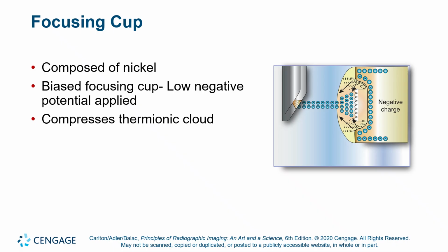Okay. Keeping the thermionic cloud, or the space charge as it's called, small allows us to keep the focal spot small. If the focusing cup is not there or it's not working, your space charge, your electron cloud, is going to bloom, that is, spread out. And then when you apply the high voltage, you'll get bombardments all over the entire surface of the anode rather than a specific focal spot. Okay? So the focusing cup is fundamental to keep the focal spot small or confined to a small space on the target anode.